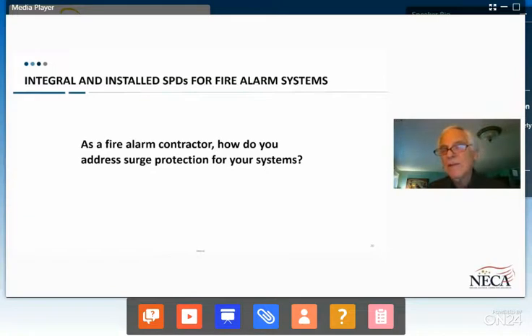So on our typical installation, we have the electrical contractor install the SPD that we provide. We have them install it in the line ahead of or immediately adjacent to our control panel or power supplies for all of the systems that we install: fire alarm, access controls, surveillance cameras, intrusion alarms, and similar systems. Where our circuits extend beyond buildings, we provide protection as required in Article 805 of the NEC. And in some cases, we will even install surge protection on individual fire alarm SLC circuits, data circuits, notification circuits, or for camera, alarm detection devices, or access control devices. So we can provide protection ahead of the panel and also down to the circuit level.